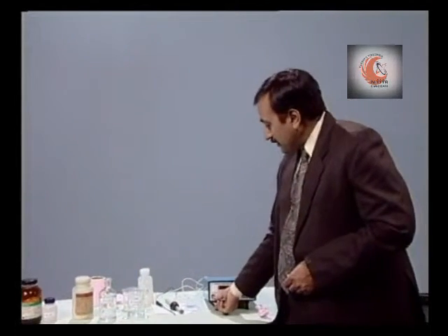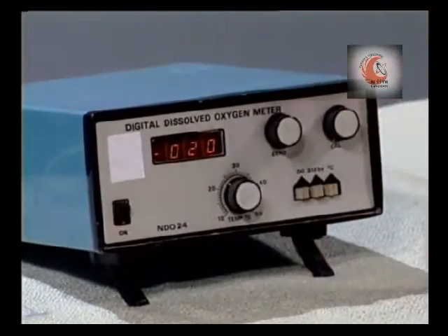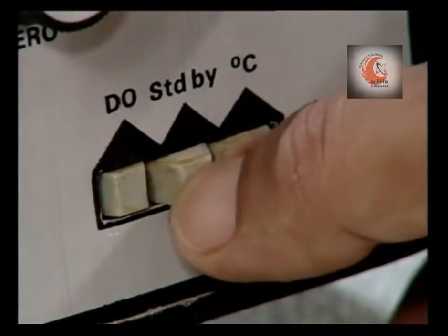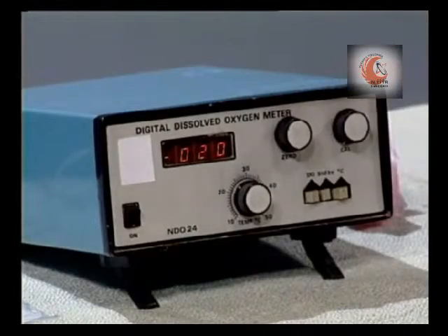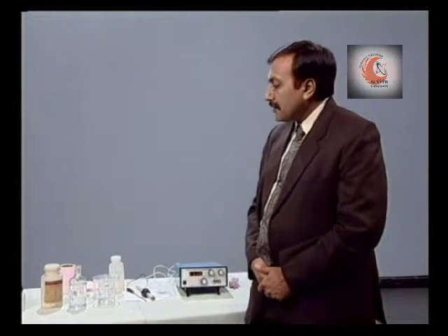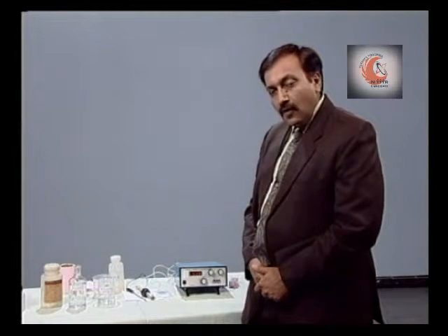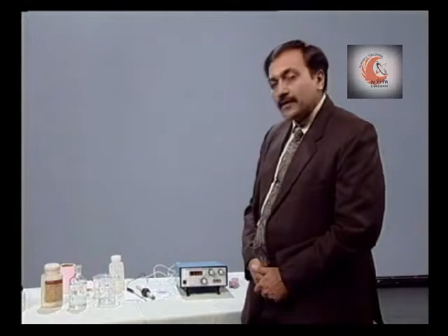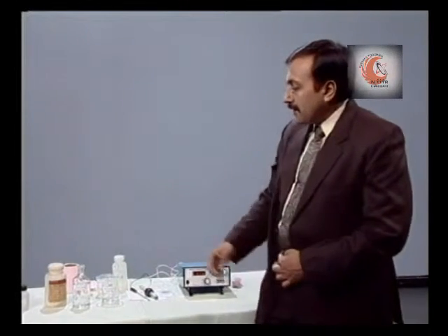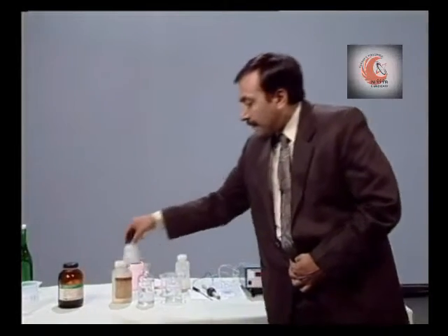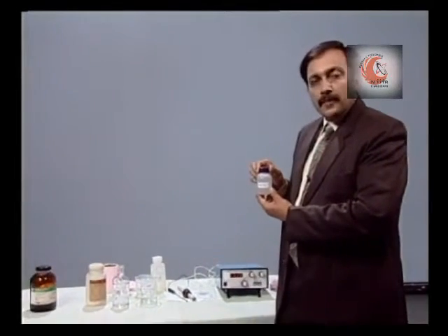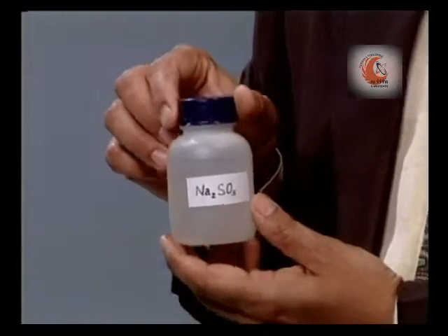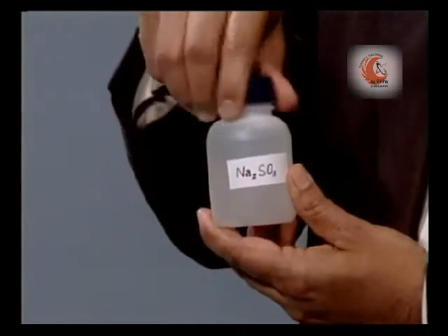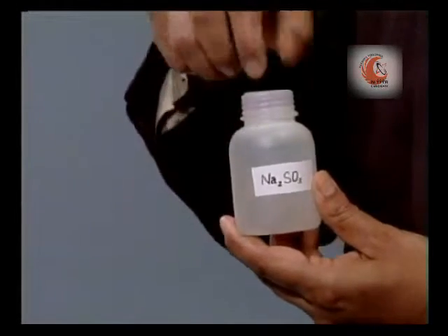Now, switch on the instrument and allow it to warm up in standby mode. Now, the instrument has to be calibrated against deionized water, of which DO value is known, and a sodium sulphite solution. The sodium sulphite solution we prepare is of 2% concentration. The sodium sulphite has 0 dissolved oxygen.